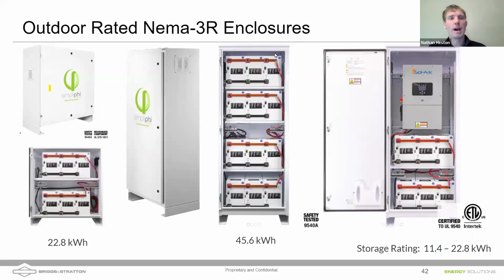Here's another view of the battery cabinet. So when you're doing outdoor installs, if you're not using that 4.98 kilowatt hour battery, we would encourage you to, of course, get a NEMA 3R enclosure. We do make and sell them. These have built-in fans that turn on if the temperature exceeds a certain limit. I think it's 110 Fahrenheit that the fan will turn on and cool.